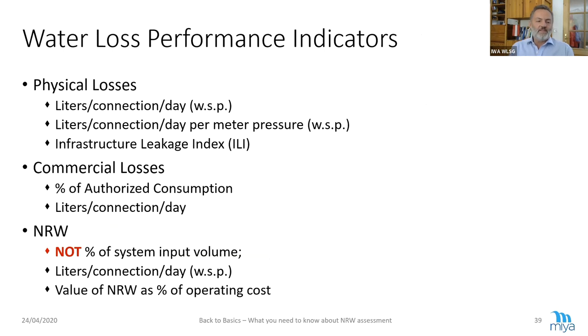Water loss performance indicators. For physical losses we have: liters per connection per day when the system is pressurized (WSP) — we always need to normalize it to get a comparable value; liters per connection per day per meter pressure; and then an excellent indicator also invented by Mr. Lambert: the Infrastructure Leakage Index, the ILI. This is by far my preferred indicator, and I'll show you later why.